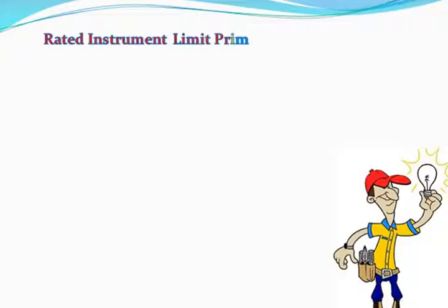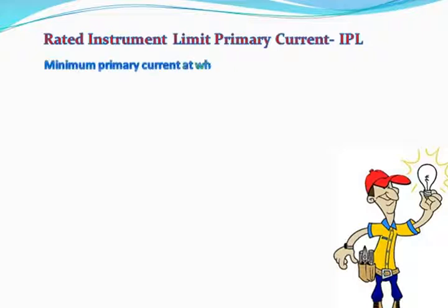Rated instrument limit primary current, or IPL: the minimum primary current at which composite error is greater than 10%.